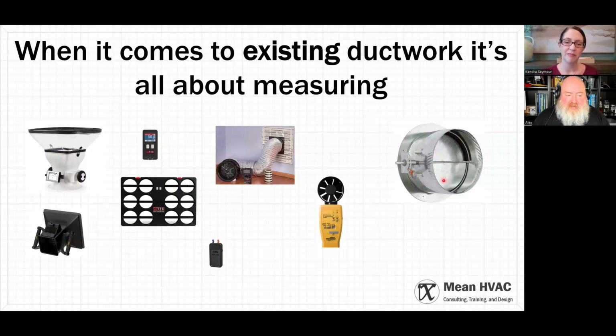The other thing that is incredibly important in a duct system is to make sure that it has adjustable dampers. Now, if I had inherited the duct system that was in my house and couldn't replace the whole thing, which is what I did—what I had to settle for in this weird scenario, since I'm not allowed to replace ductwork—is disconnecting every branch run and putting one of these in it.